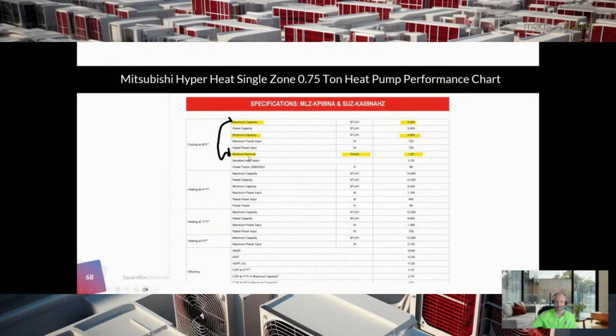One thing you have to pay attention to is that moisture removal is rated at full capacity. So once these things start turning down, what do you think's happening to the ability to remove moisture? It's proportional, just like any other piece of equipment, 70-30, where about 70% of your capacity is going to sensible and about 30% to moisture removal. And so that capacity drops as the sensible capacity gets down to 48%. Then you're at about 30% of that or less with your moisture removal. So it gets very, very small. You have to pay attention to that when you're using these smaller pieces of equipment, else you're going to get into trouble with your dehumidification. You're going to start having moisture problems and not know where they're coming from.